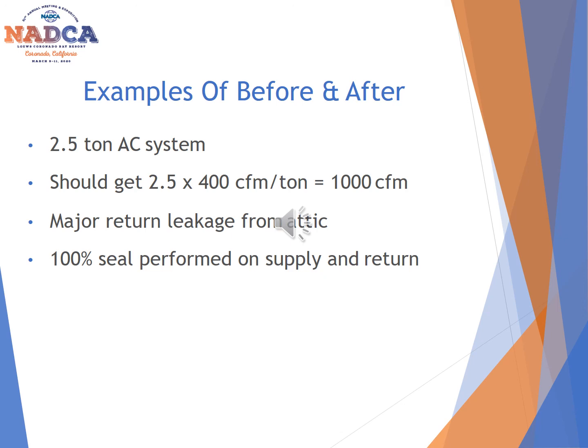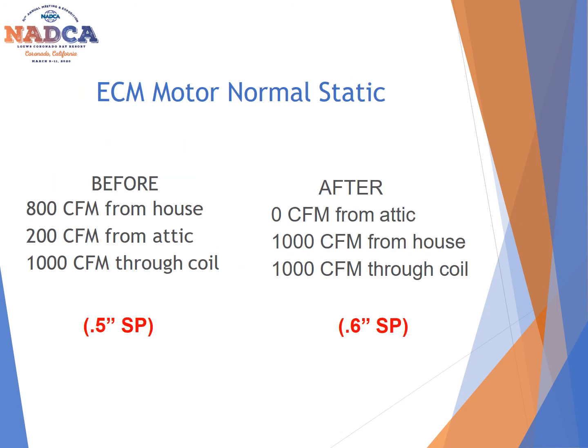In this particular situation, we have a 2.5 ton AC system. And if you figure that you should get about 400 CFM per ton, this system should be able to produce about 1,000 CFM. In this scenario, we have an ECM motor, which is also known as a variable speed motor. And in the house, before they did any type of sealing, they had about 800 CFM coming from the house and 200 CFM coming from the attic. Of course, that passed through the coil and then back into the house again. After they were done sealing everything, you had zero air coming from the attic itself, and 100% of the CFM, the 1,000 CFM, was coming from the house, through the return, going through the coil, and back into the house.